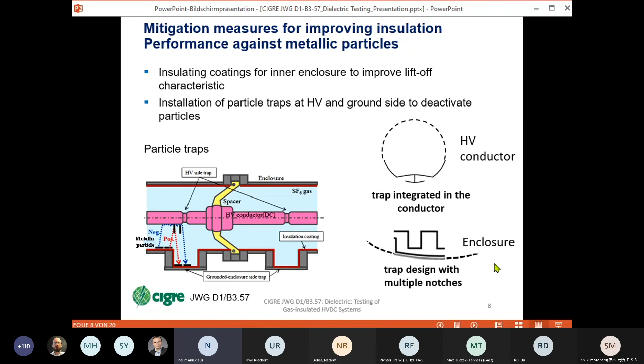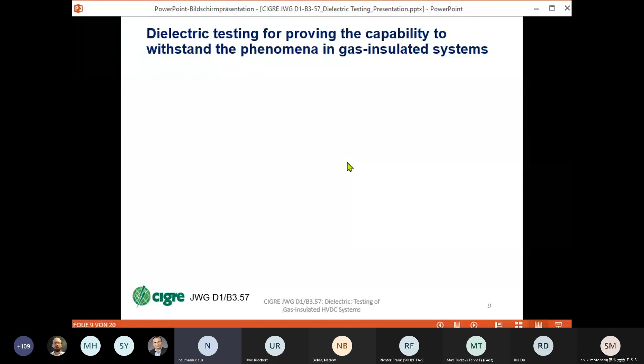Yes, what can we learn when we want to prove the capability to withstand these phenomena I've mentioned in the gas insulated system? First, we want to consider the insulator in the gas insulated environment. If we energize the gas insulated system, we have to consider this interface charging of the solid gas surface and the space charge accumulation in the solid insulation until the resistive steady state is reached. And this transition to the DC field distribution depends on the local temperature distribution and on the lowest temperature. And this transition could lead to a long test duration of hours or months.